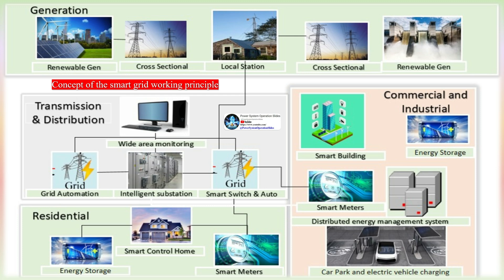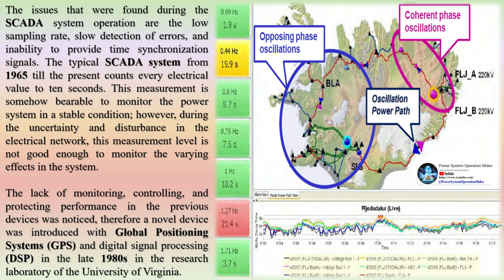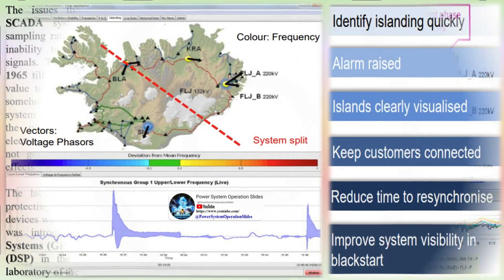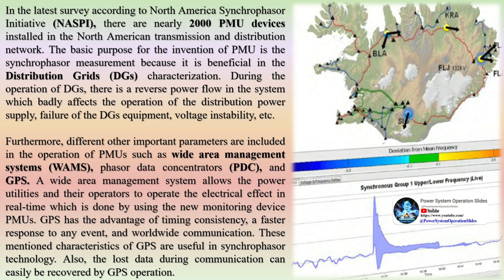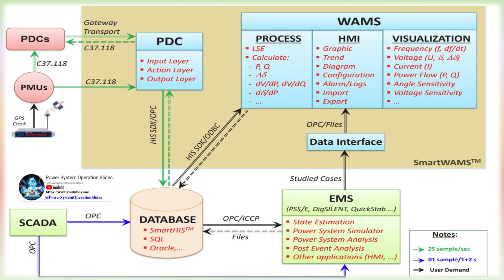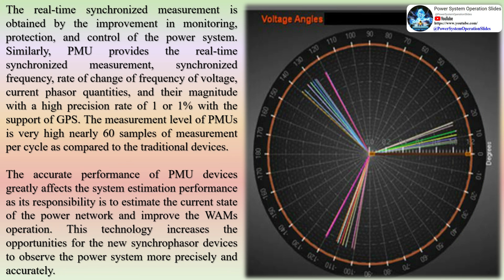A wide area management system allows power utilities and their operators to operate the electrical grid in real time using the new monitoring device PMUs. GPS has the advantage of timing consistency, a faster response to any event, and worldwide communication. These characteristics of GPS are useful in synchrophasor technology. Also, lost data during communication can easily be recovered by GPS operation. WAMS are based on the new data acquisition technology of phasor measurement and allow monitoring transmission system conditions over large areas to detect and counteract grid instabilities. Current, voltage, and frequency measurements are taken by PMUs at selected locations and stored in a data concentrator (PDC) every 100 milliseconds. The measured quantities include both magnitudes and phase angles and are time-synchronized via GPS receivers with an accuracy of 1 microsecond.